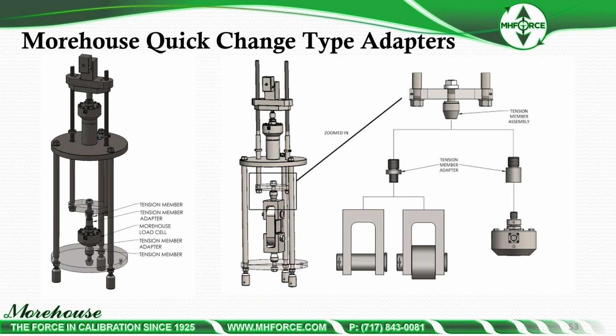So here are some pictures of adapters. We've adopted ISO 376 here. If you look at this, this is our quick change tension member adapters. In most cases, there's a spherical here, and there's a spherical down here. Here it's shown with a clevis, probably an ED dynamometer, where if you've seen our other webinars, you know the pin size in these makes a huge difference. But in any case, this adapter system, not only for load cells, but for other dynamometers, crane scales, whatever, will keep that line of force as pure as it can be.